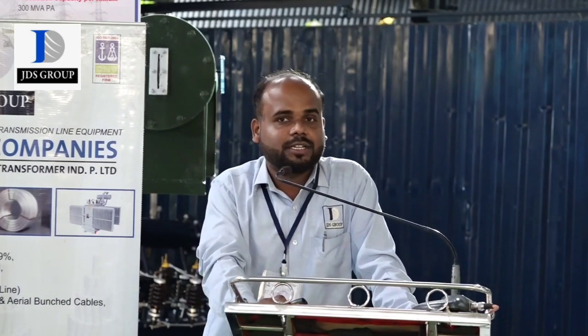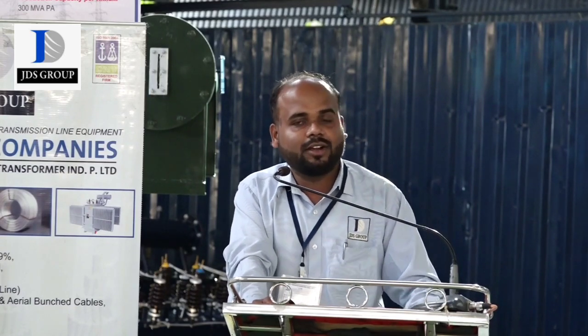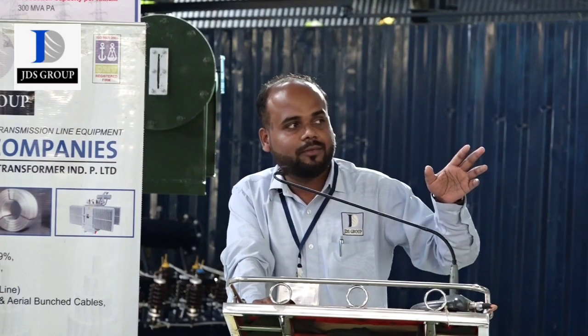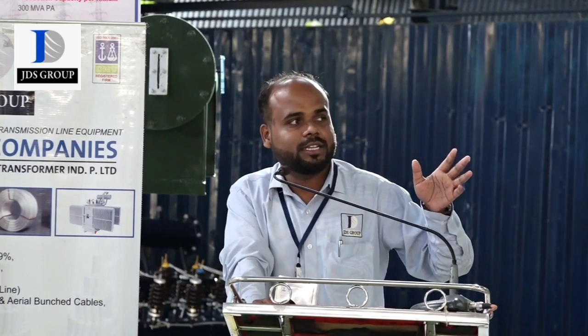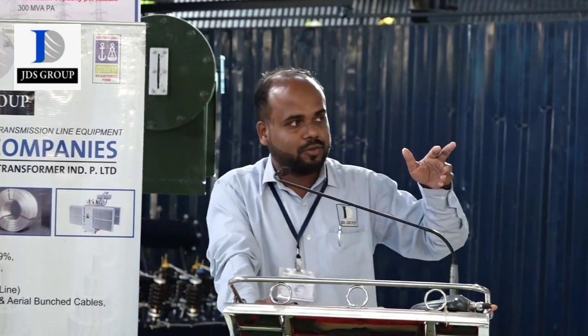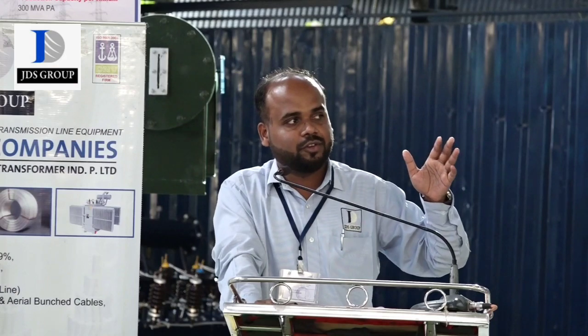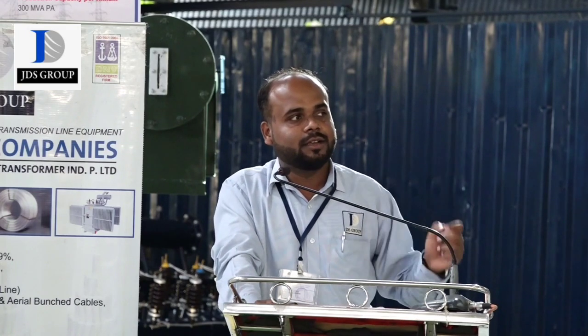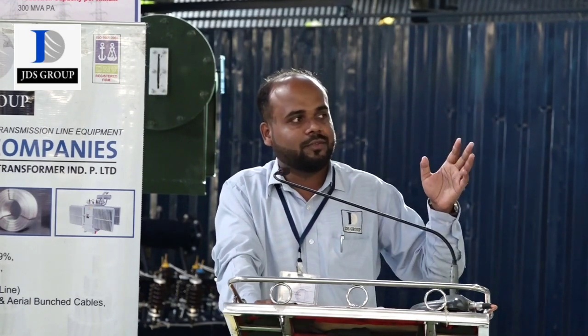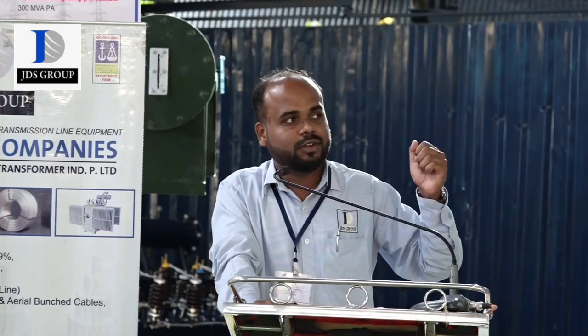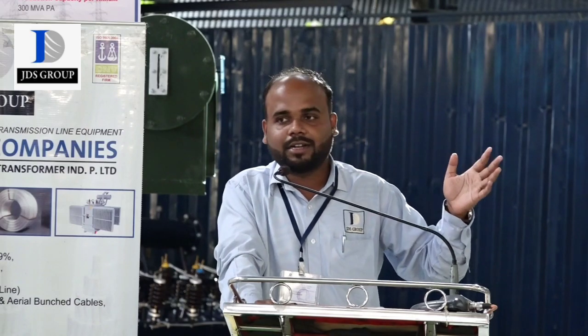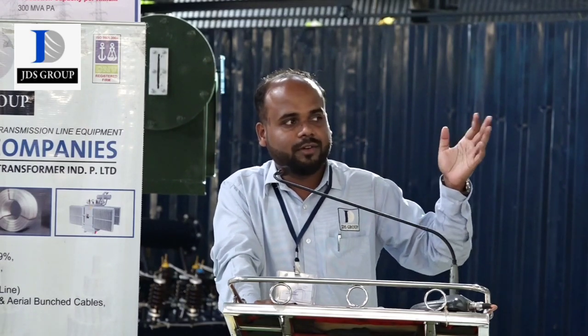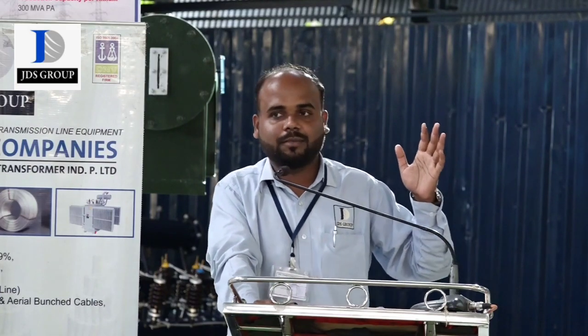Another test is the voltage ratio test. As I said, our HV voltage is 11 kV and our LV voltage is 0.433 kV. So we check whether we are getting the exact voltage or whether some different voltage is given. By the voltage ratio test, we measure the voltage ratio of the transformer. For example, V1 by V2 equals N1 by N2, where V1 is the voltage of the primary side, V2 is the voltage of the secondary side, N1 is the number of turns in the primary side, and N2 is the number of turns in the secondary side. For example, for our 100 kVA distribution transformer, the primary side voltage is 11 kV, meaning 11,000 volts, and V2 is 0.433 kV, meaning 433 volts. Dividing 11,000 by 433, we get a ratio of about 25.4. So this is the voltage ratio, which means our transformer voltage is correct.